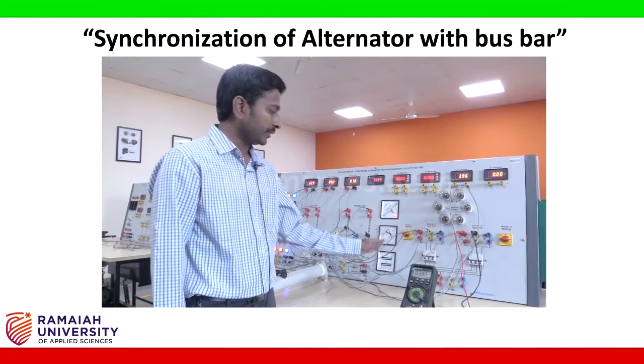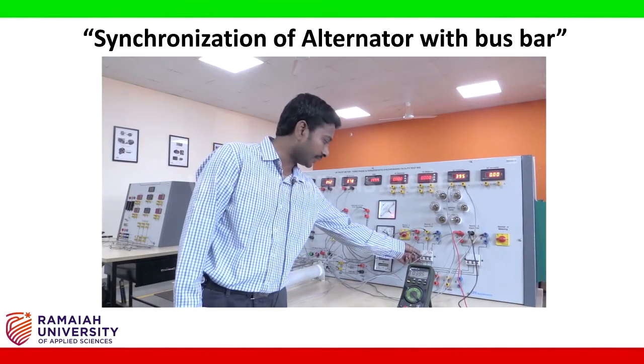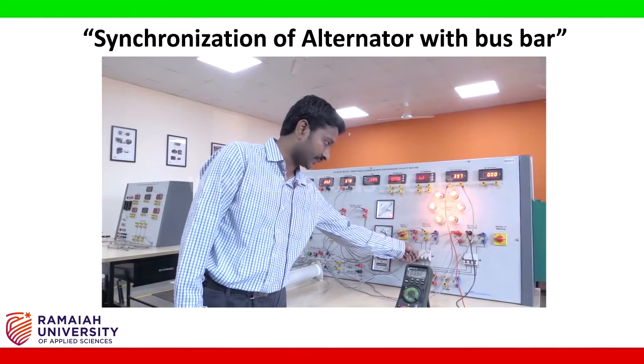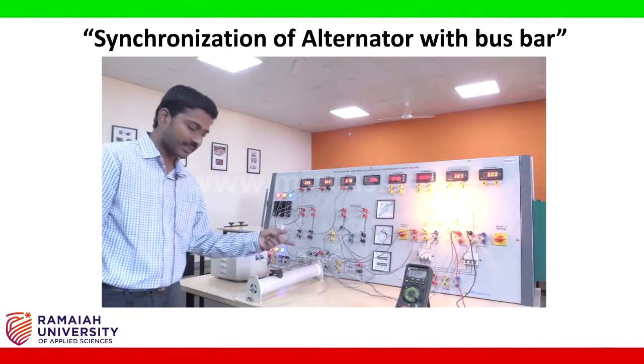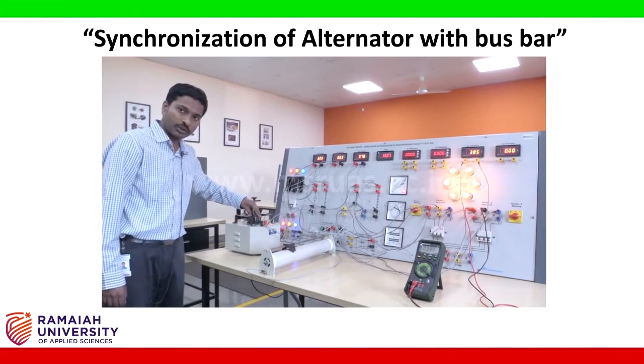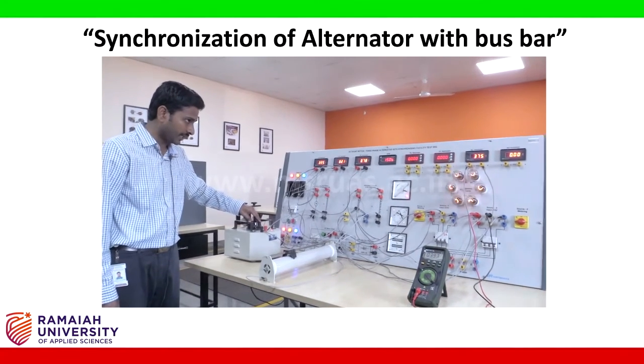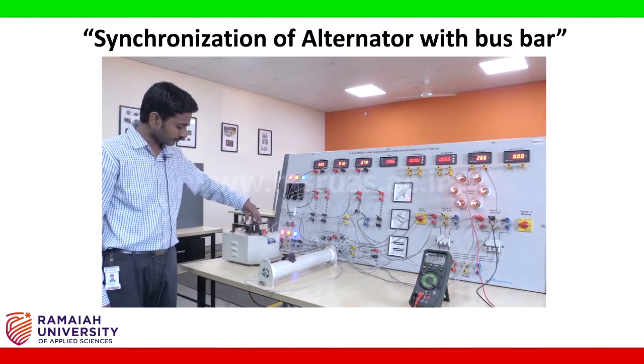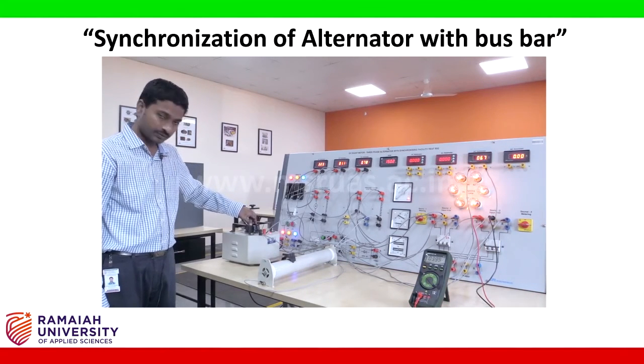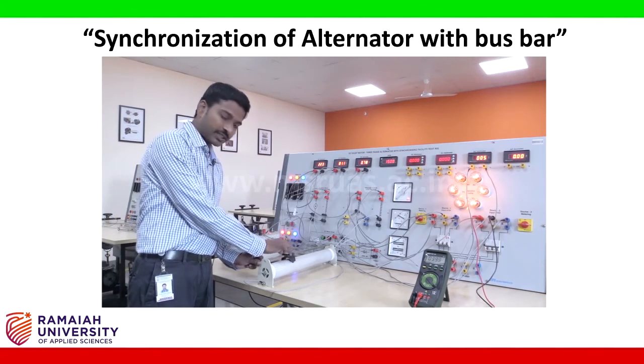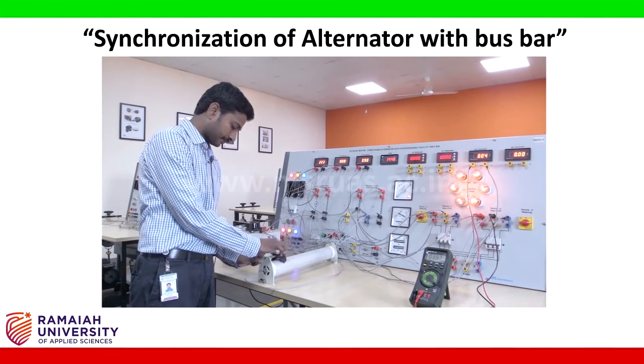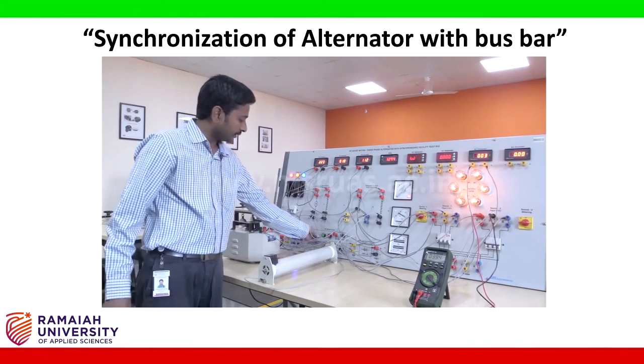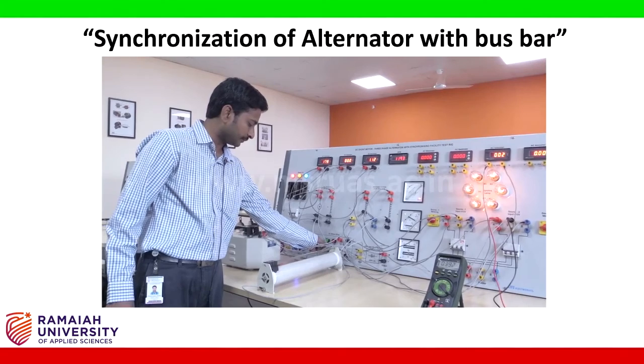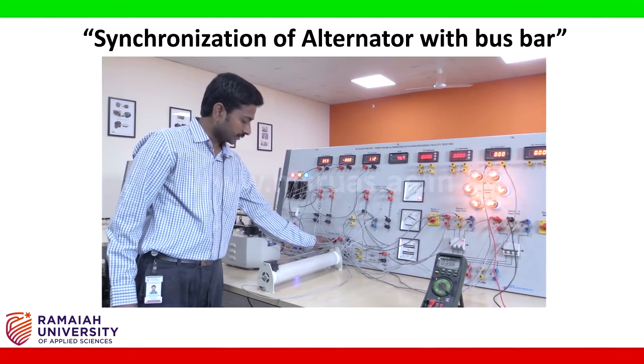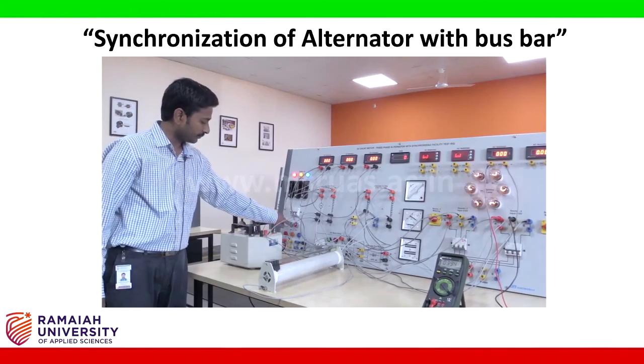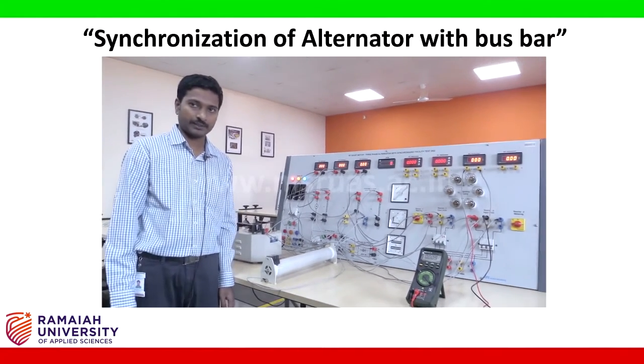This completes the experiment. To turn off the system, first break the synchronism with the infinite bus. To break the synchronism, first open the synchronizing switch. After closing the synchronizing switch, bring back the alternator voltage to 0 by reducing the field rheostat of the alternator. Then bring back the rheostat to minimum position. Reduce the armature voltage to 0. Turn off the power supply. Push button. This completes our experiment.